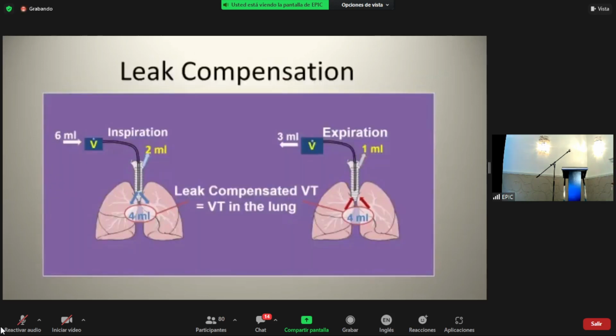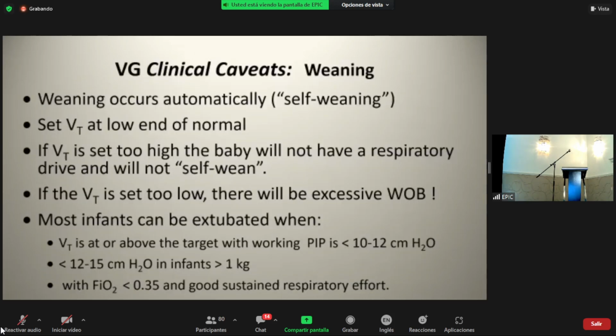Just one word about weaning, which has to do with the fact that volume targeted ventilation will lower pressures automatically as long as the tidal volume is set appropriately. Obviously, if it's too high and the baby's alkalotic, they're not going to breathe. They're going to ride the ventilator. But if the tidal volume is too low, the work of breathing will become excessive and actually can lead to collapse of the lungs, and that's probably not what we want to achieve.